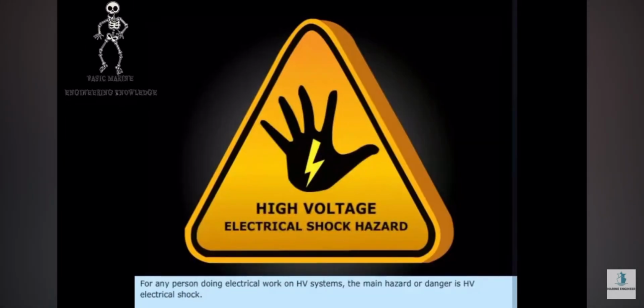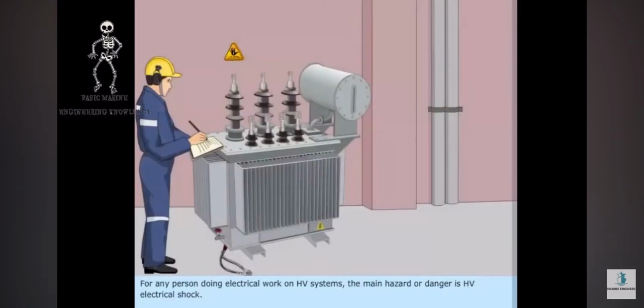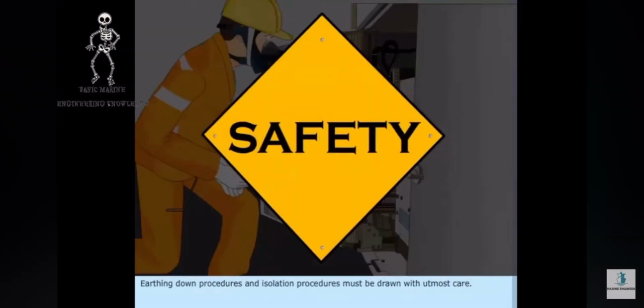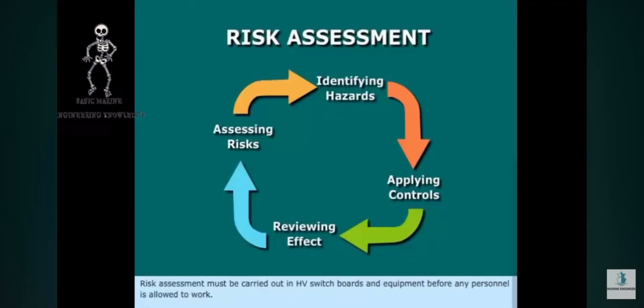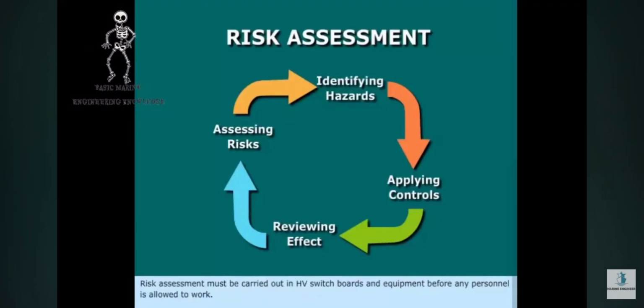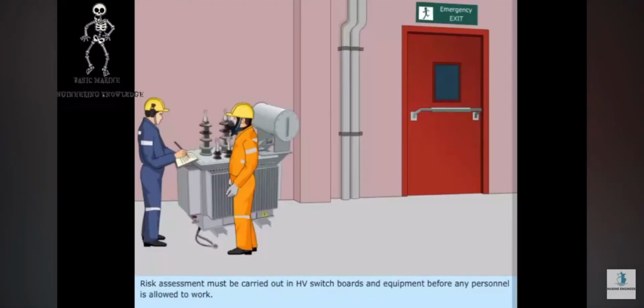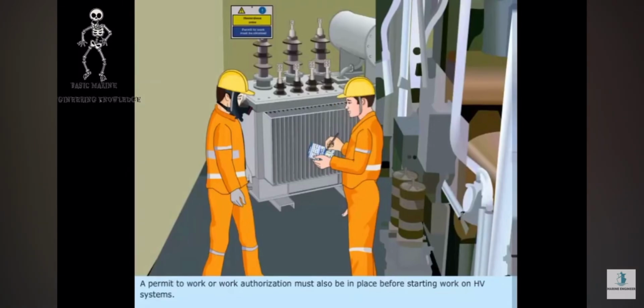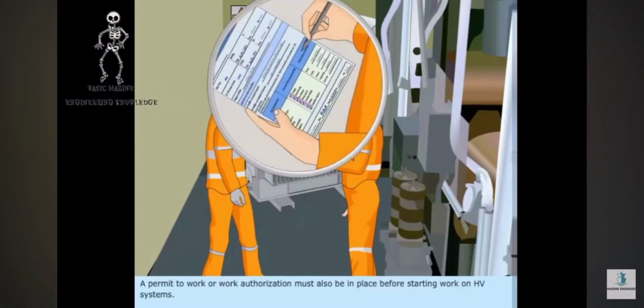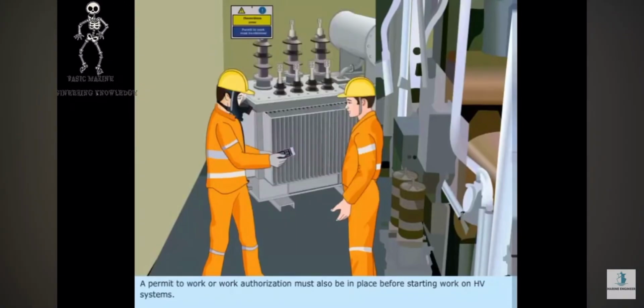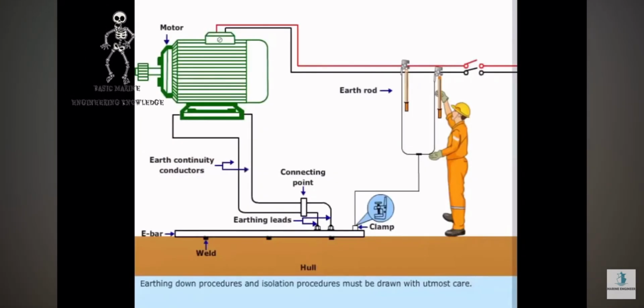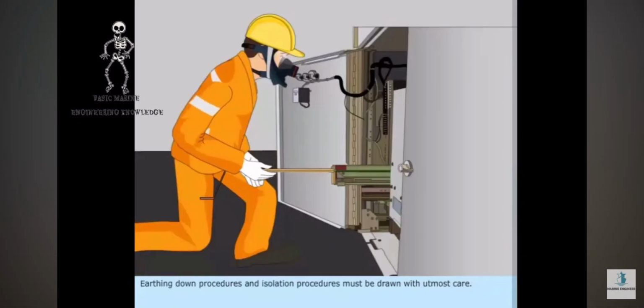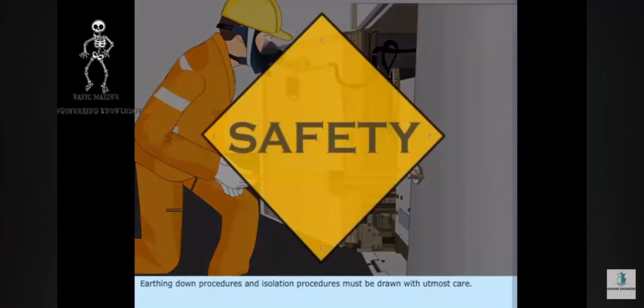The main hazard or danger of electrical work on a high voltage system is high voltage electrical shock. So, personnel at work must keep in mind safety first. Risk assessment must be carried out on the high voltage switchboard and equipment before any personnel is allowed to work. A permit to work or work authorization must also be in place before starting work on a high voltage system. Earthing down procedures and isolation procedures must be drawn up with utmost care.